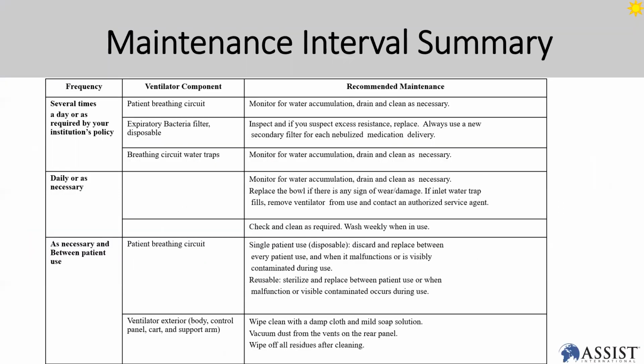Okay, preventive maintenance. This is a very important part of it. Currently, you have quite a lot of ventilators used in the hospital, but you need to maintain them to make sure they perform during this period and work properly. For the interval maintenance, you normally need to know the patient breathing circuit, all these need to be looked after properly and make sure they work properly. And if single use, make sure you clear them. You also have to monitor the water trap. Very important, because you don't want the water trap to create issues with too much water.